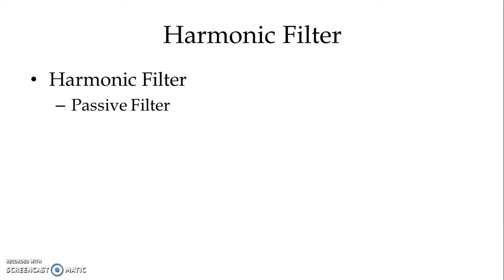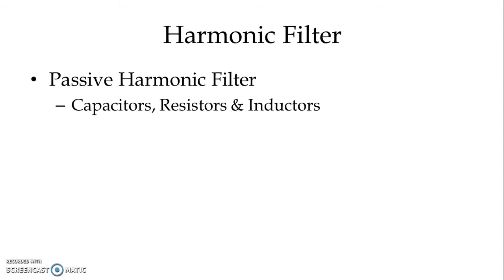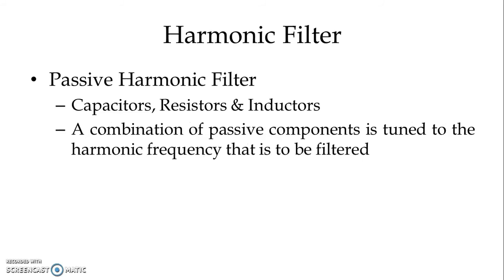We have a harmonic filter. Broadly, if we classify it, we have passive harmonic filters as well as active harmonic filters. In passive harmonic filters, as the name indicates, we use passive elements like capacitors, resistors, and inductors. A combination of passive components is tuned to the harmonic frequency that is to be filtered.